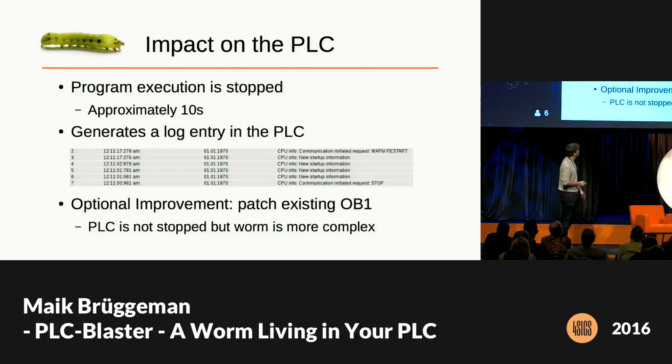Okay, that was the demo part. Now back to the slides. Now the question is, what is the impact on the PLC? We saw that the program execution is stopped for approximately 10 seconds, and this generates a log entry in the PLC. You are able to recognize that something strange is going on. But you can improve that because you can patch existing programs.